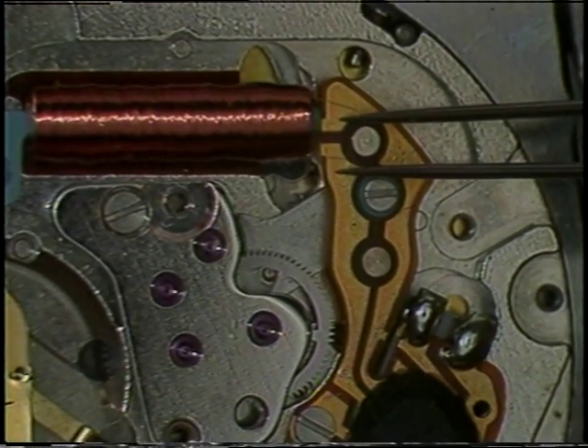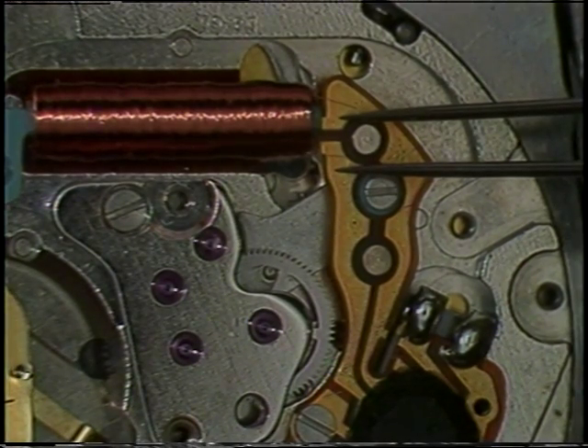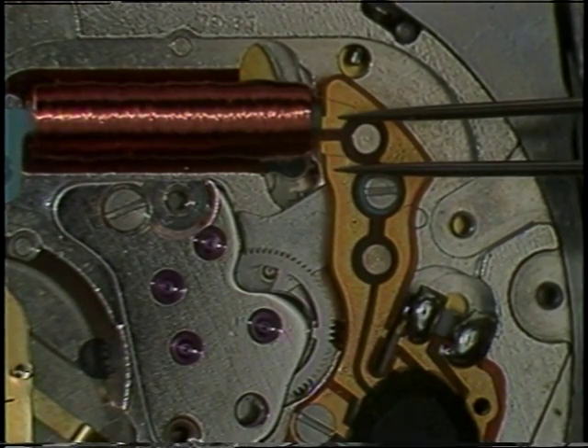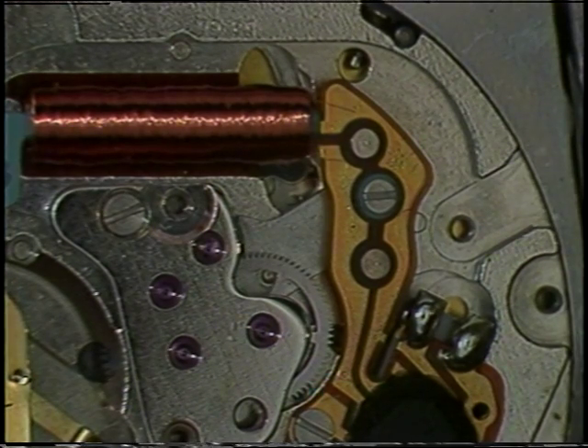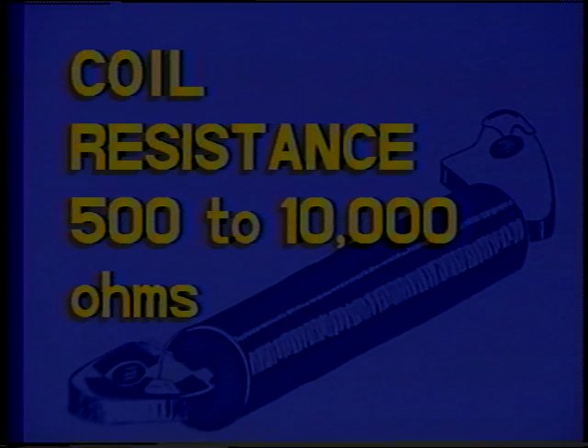It will not buzz if the coil is broken or if the coil terminals are shorted together. It only buzzes when the coil resistance is between 500 and 10,000 ohms.